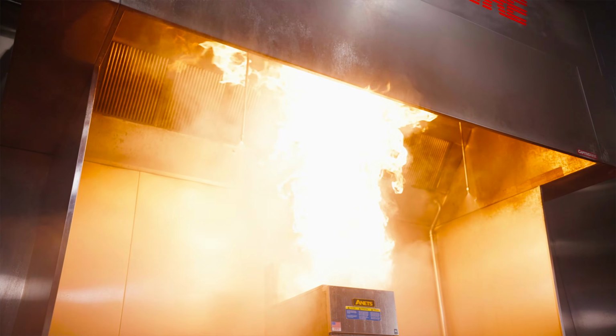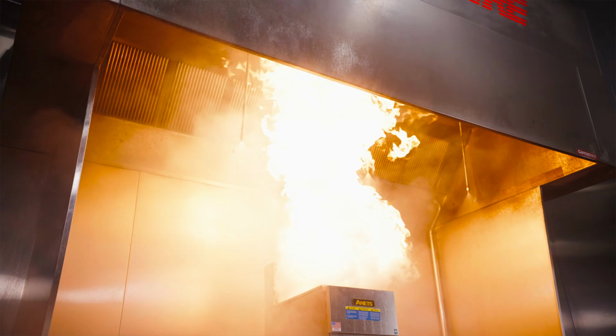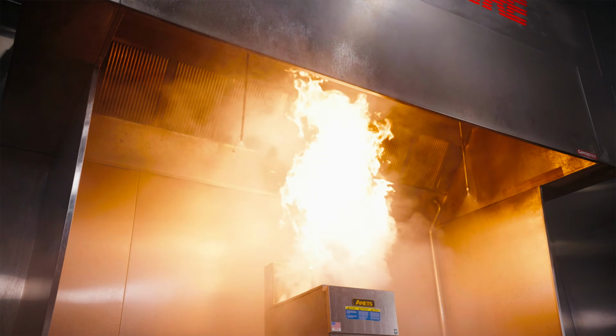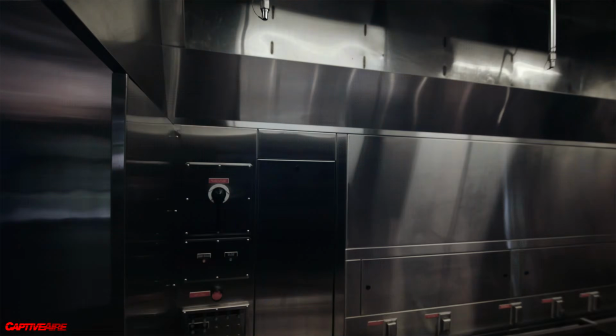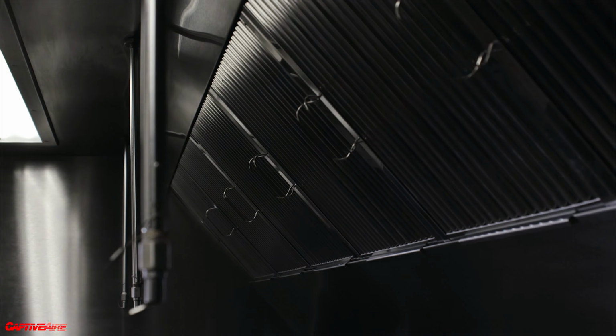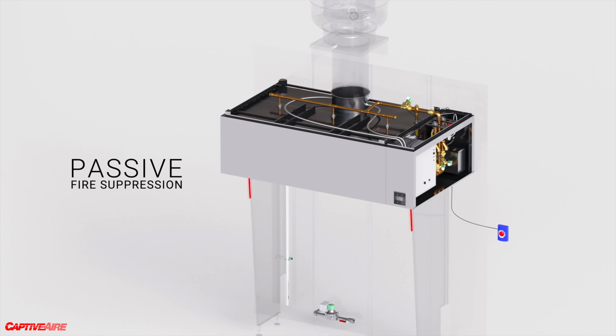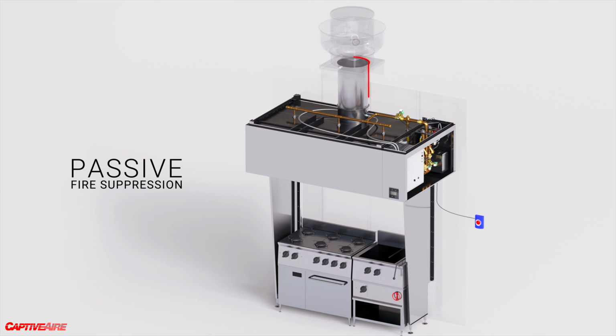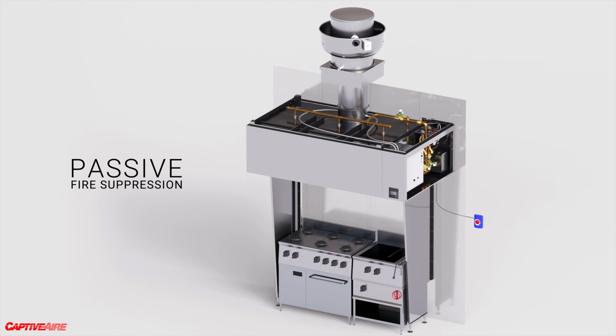There are different ways to look at fire suppression. One is active - the fire suppression system itself dumping agent onto the fire. The second is passive. When I say passive fire suppression, I mean how we are designing the hood around the appliances, the ductwork, and the fan to hold up in a fire.